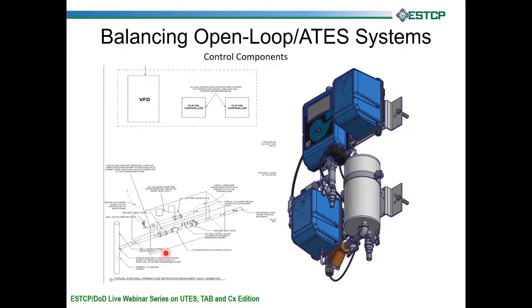So the way we've done it is we use an injection valve, which we've covered in previous webinars, and we use this injection valve to do 2 things: to control pressure and to control max flow. And doing those 2 things, most of the time we can get that flow evenly split. So here is a diagram of our well. Here's our well casing coming up from below grade. Here's our horizontal ATES pipe, which is bidirectional. We have a water meter in here. That water can only flow one way through, so we have to have this bypass. When we're extracting water out of the well, we would bypass around the flow meter and go out.